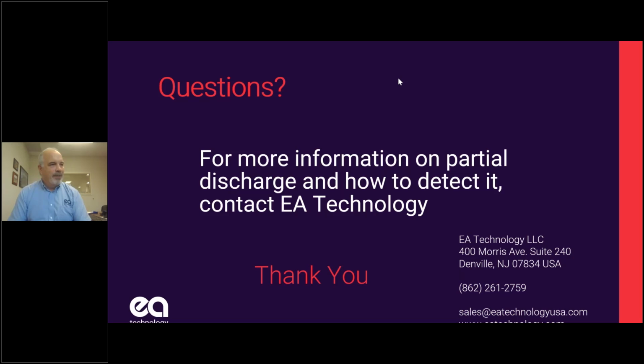Oh, that's absolutely right. I didn't mention that, but remember, we've got this engineered system. We've got insulation of a certain width, and it's all designed to contain the field within the shield. If I do anything to affect the integrity of that insulation, such as a bend radius violation, the insulation at the bend is going to be compressed. On the outside it's going to be stretched, and on the inside it's going to be pressed. It's going to change the size of that, and now I've got an electric field distribution that is different. The insulation may be smaller, or kinked, or may generate a gap. So anything that mechanically affects the insulation can cause PD.